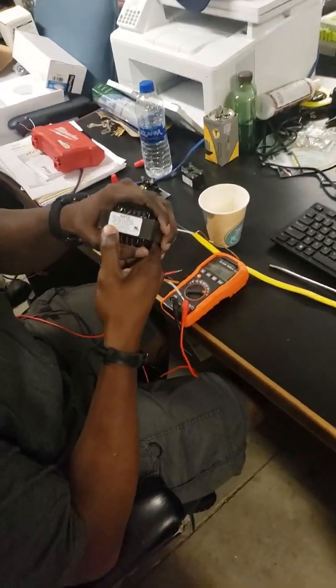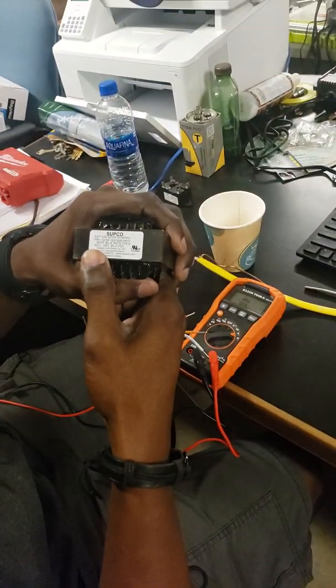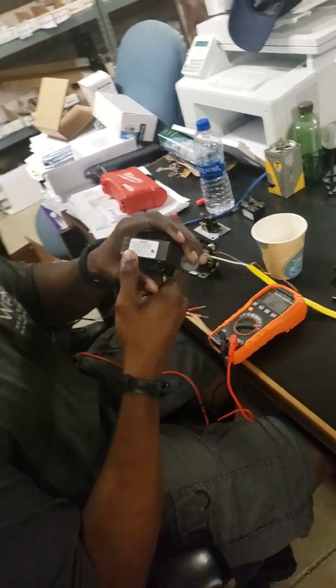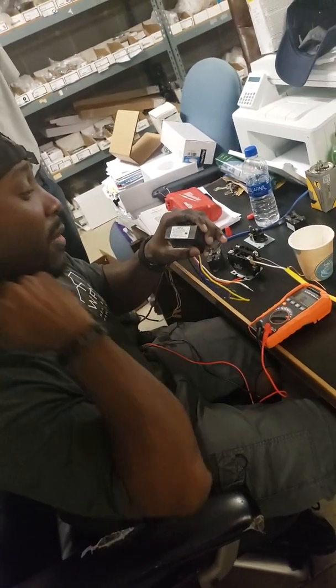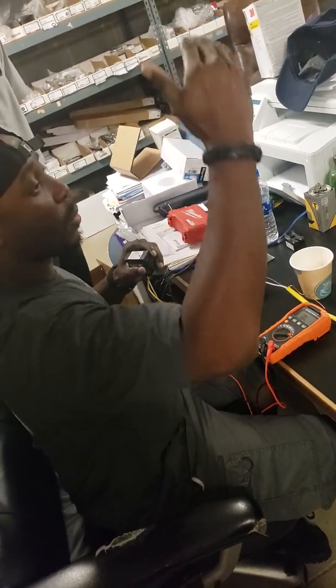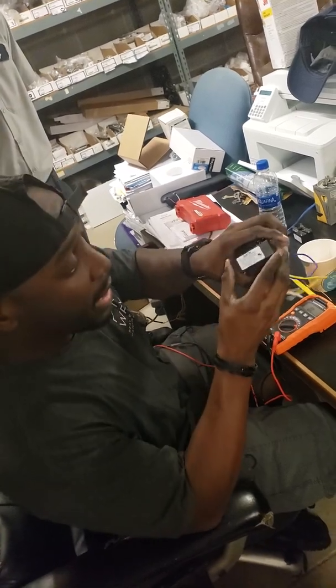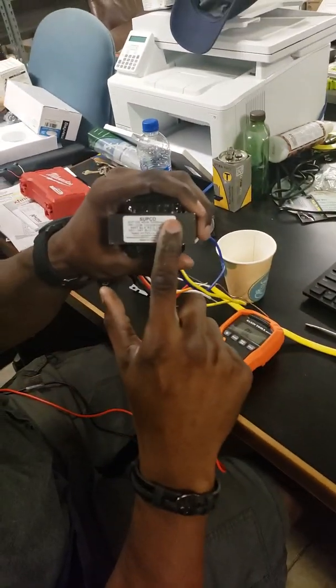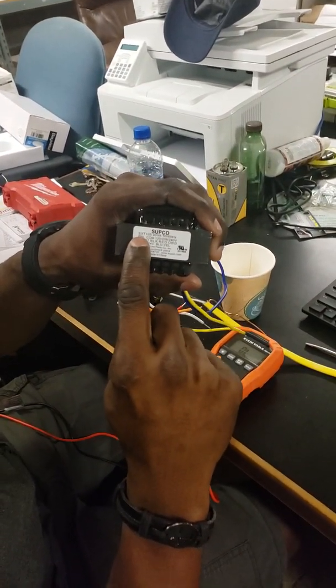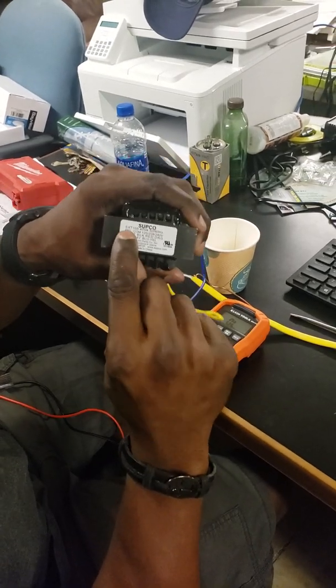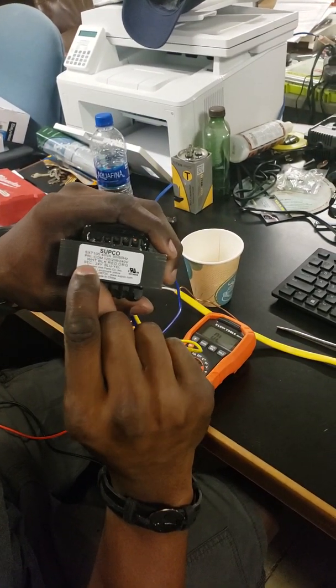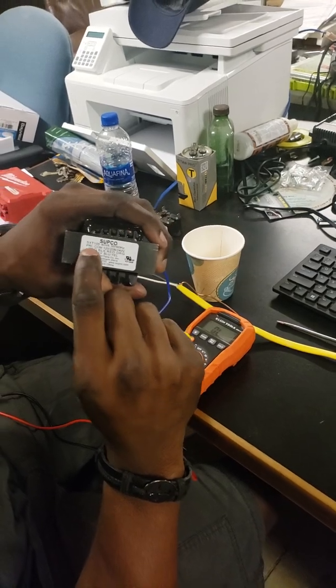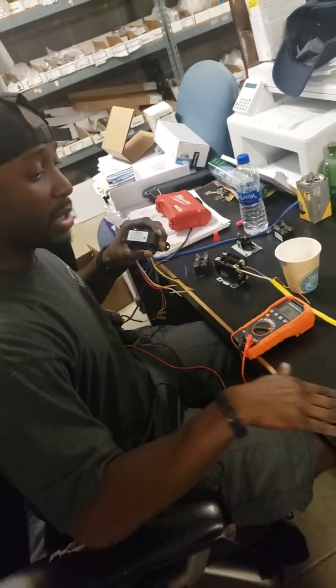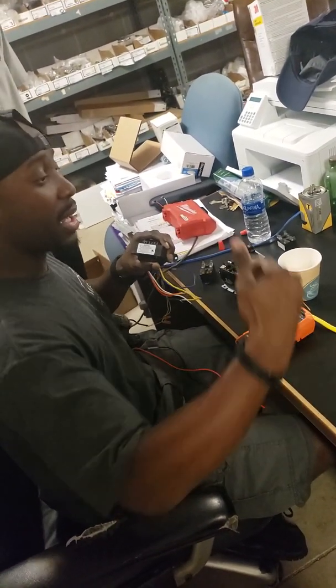Now this is one of those transformers that can be used for multiple voltages. It can step down multiple voltages versus just going from 120 to 24 volts. If you look at the transformer, the first thing you want to do is identify the primary and the secondary. Primary is going to say PRI, secondary is going to say SEC.